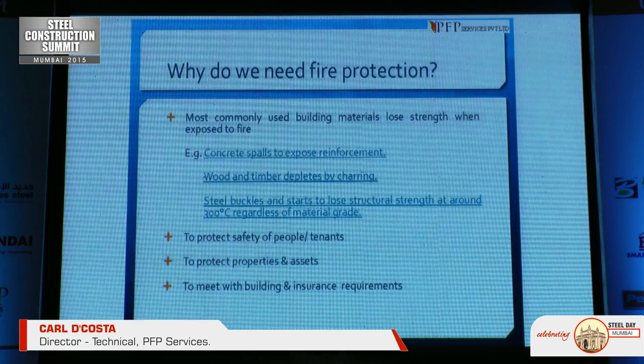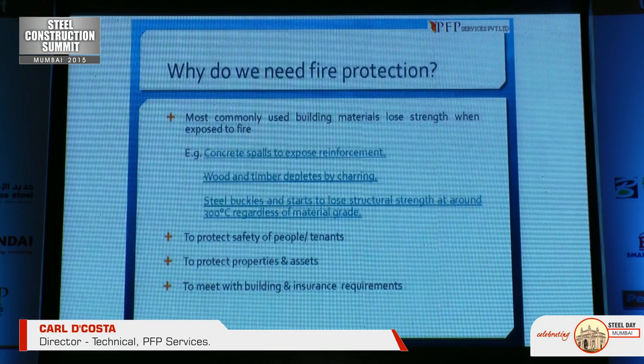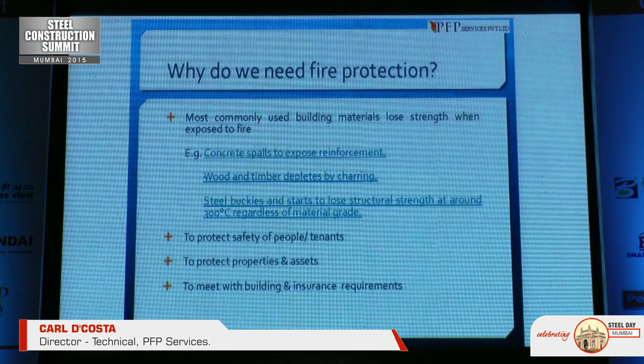Most commonly used building materials lose strength when exposed to fire. Concrete will spall to expose its reinforcements. Wood and timber deplete by charring. Steel buckles and starts to lose structural strength at around 300°C, regardless of the type of material used. Protection is needed to ensure safety of occupants, protect properties and assets, and meet building and insurance requirements.